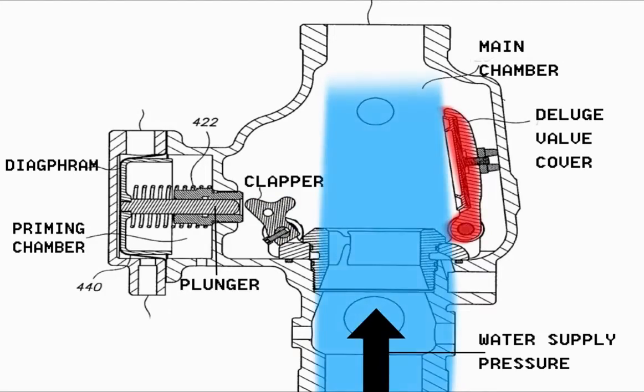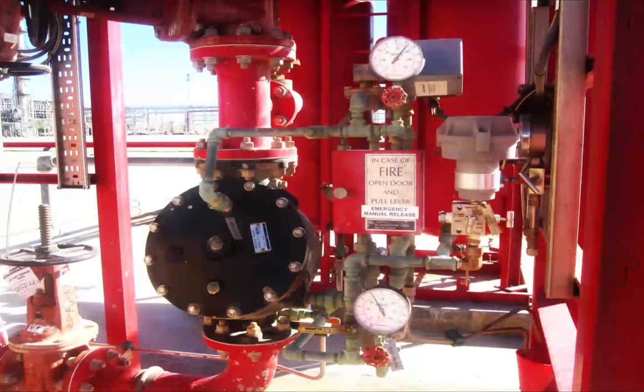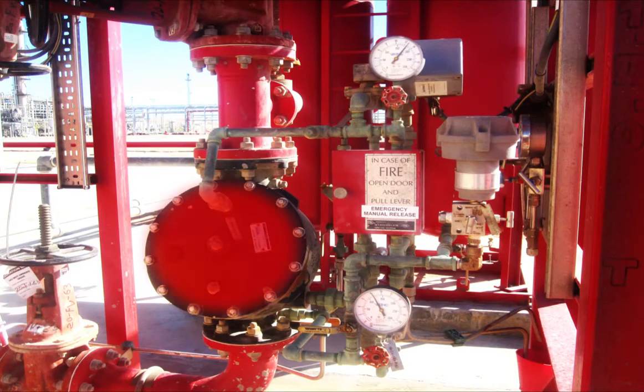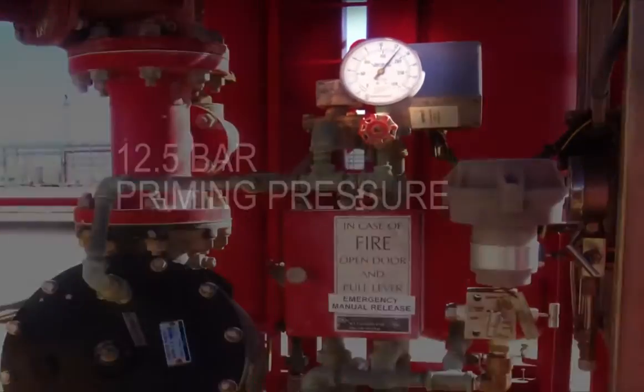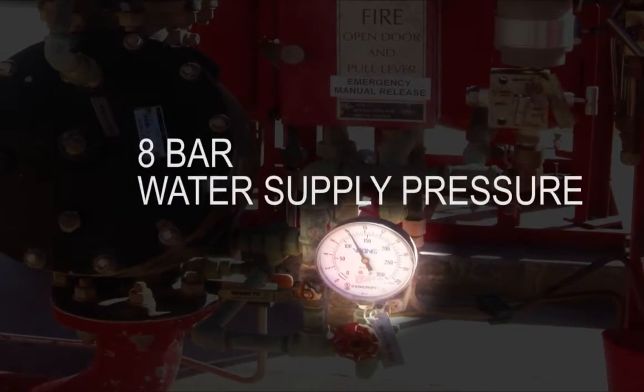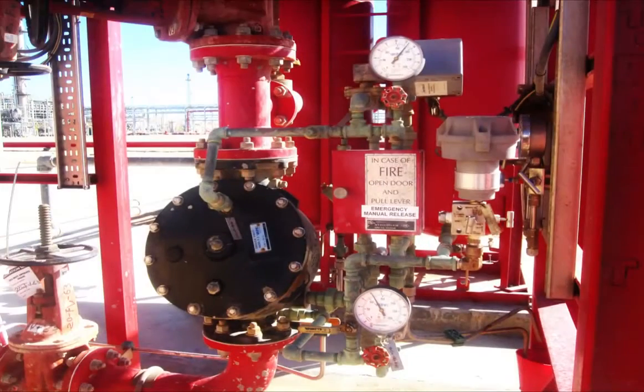This photo shows the deluge valve in the normally closed position, where the priming water pressure is 12.5 bar while the water supply pressure is 8 bar. The priming water pressure branches from the water supply pressure, so normally there should be a zero differential pressure between them, which is essential for the deluge valve to remain closed.